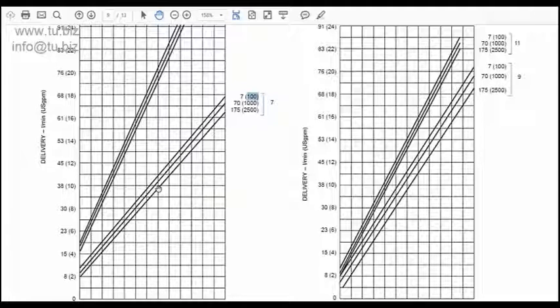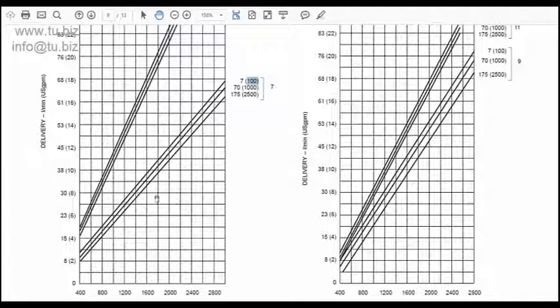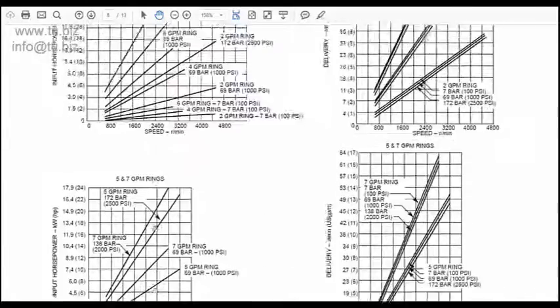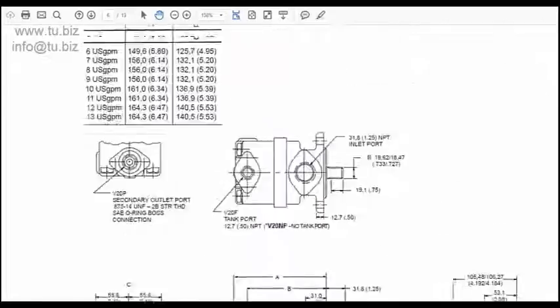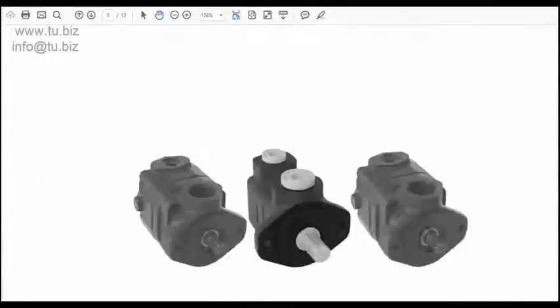I'm not working at 2500 PSI — I'm working at 2000 PSI, so the actual flow will be higher, maybe 10 GPM or a little more. The curve doesn't explicitly show the 2000 PSI line — it only shows 1000 and 2500. At 1000 PSI the flow would be slightly higher than 10 GPM. I think this pump will be okay, but I want to check whether I should go to a higher cartridge size.